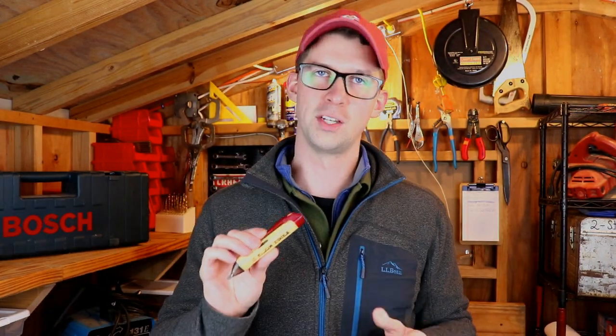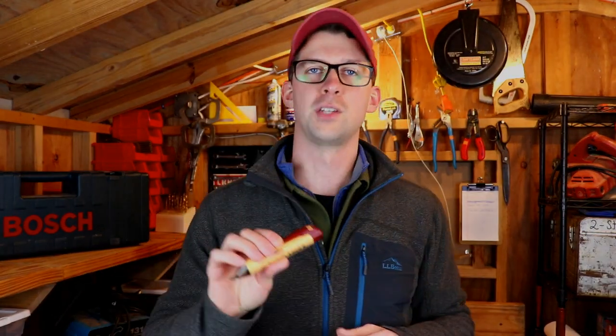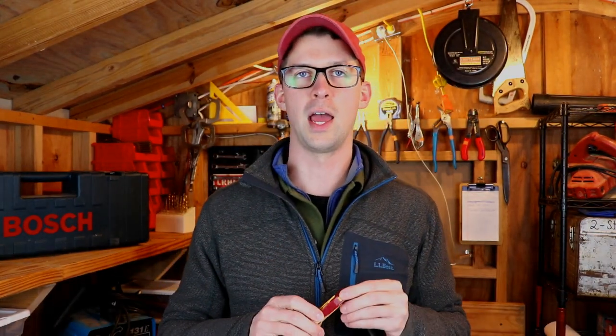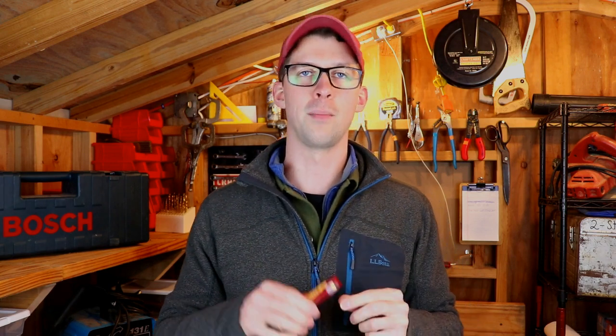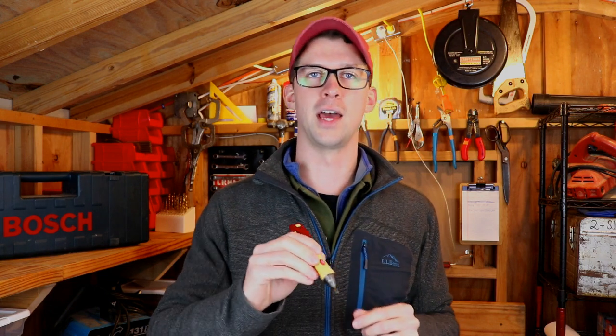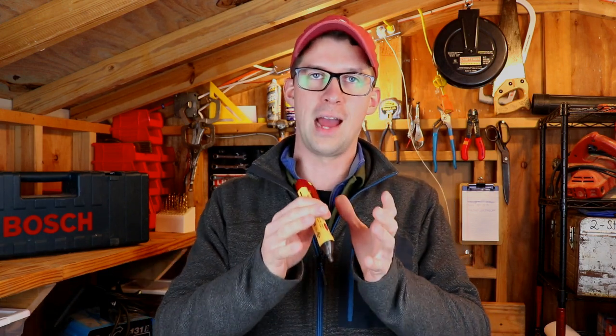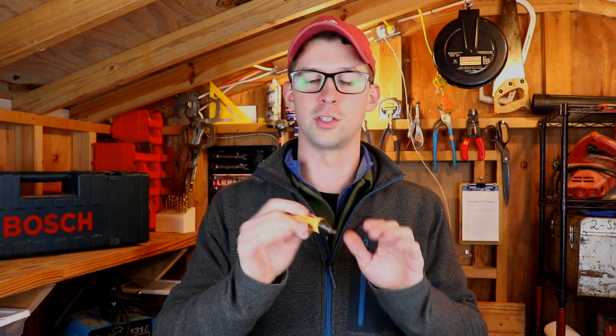Let's dig in. So when does this tool come into play? Say I want to replace an outlet or a switch and the circuit is hot. I flip the breaker off and I'm ready to unscrew that cover and dig into the outlet to repair it. I want to make one last safety check to make sure that circuit is dead, that I didn't hit the wrong breaker, or that somebody else told me the breaker's off and I'm not just trusting them — I can confirm right there at the outlet as I'm working on it that it is in fact cold, that there's no electricity to it.